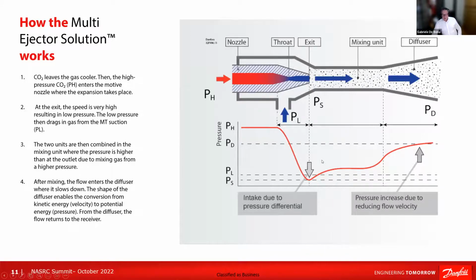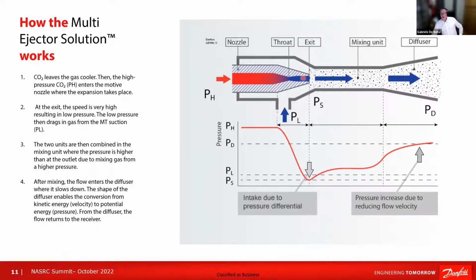How does it work, briefly? As Miguel was saying before, I'm not going to go deep into how the ejector works. We have literature and training on our site that can explain it more efficiently than I can. Basically, the important thing to say is that the high pressure gas coming from the gas cooler goes through the nozzle. Let me change the pointer, sorry. Okay, going through the nozzle here, it starts to expand and gets a boost in speed. This creates a pressure drop that drags in the gas from the medium temperature suction line. The two gases then mix in the mixing unit and go back to the liquid receiver through this diffuser.